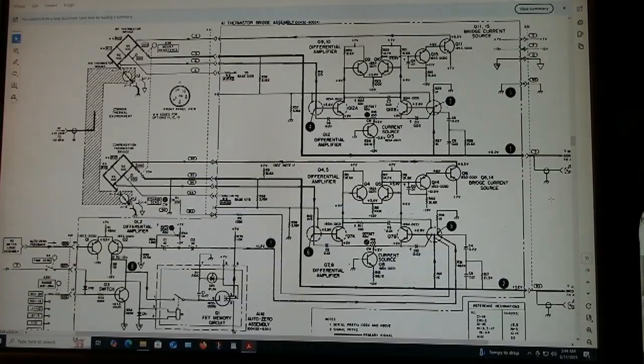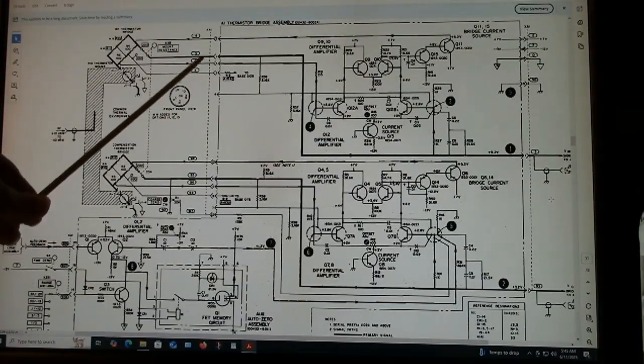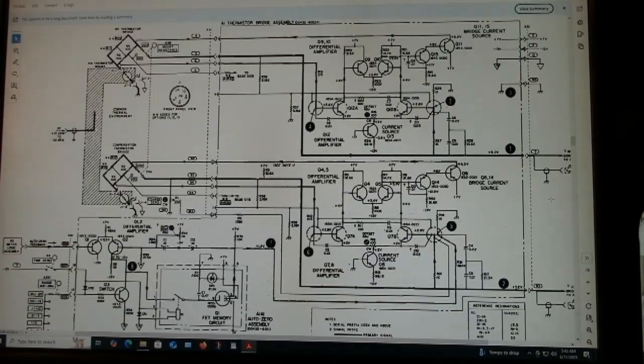This will be a brief description of the circuit operation of the 432A power meter here. This is a schematic of the A1 module in the unit here. And to the left of this dotted line, this is in the thermistor mount here. There's two thermistors, one up here. This is the one that measures the incoming RF power, and the thermistor on the bottom here is used to measure ambient temperature here. And the reason they do this is that as you use this device here, as the ambient temperature in the room that you're using it varies, these two thermistors will both vary equally.